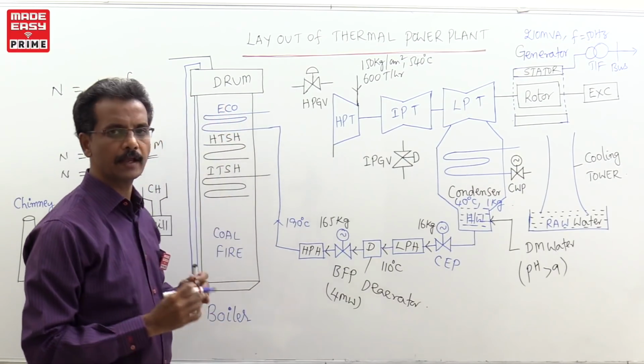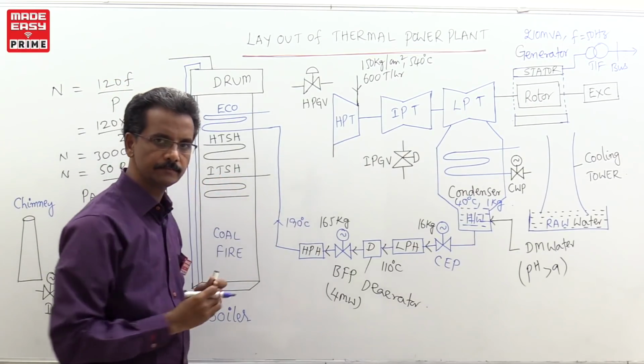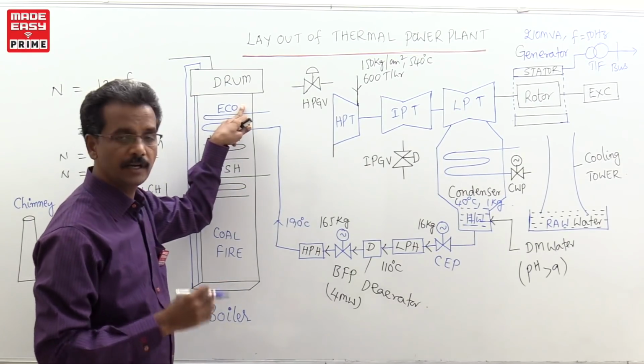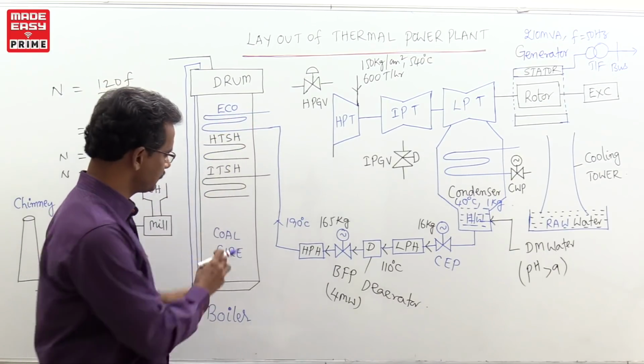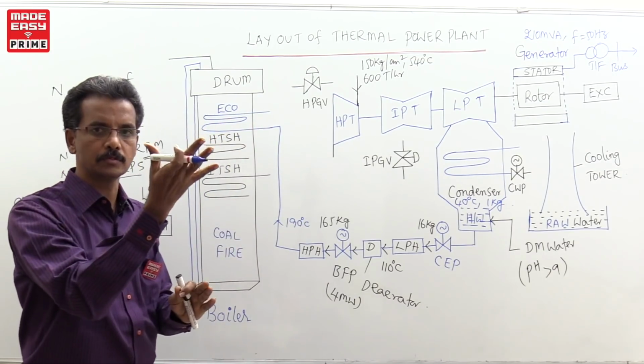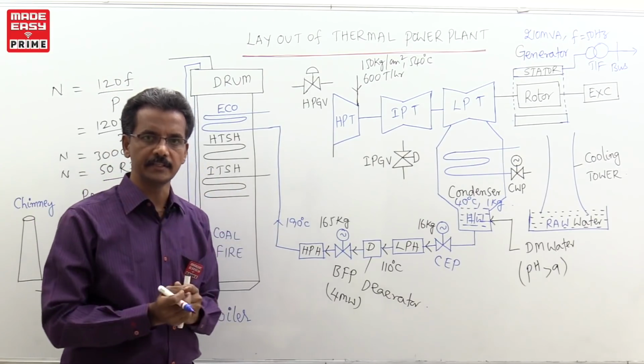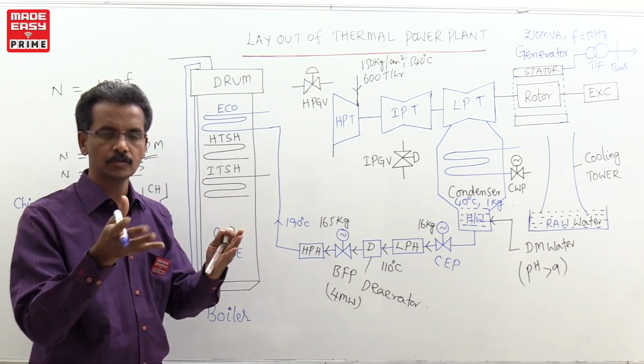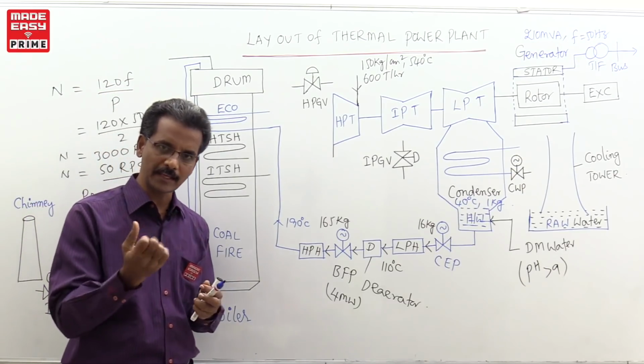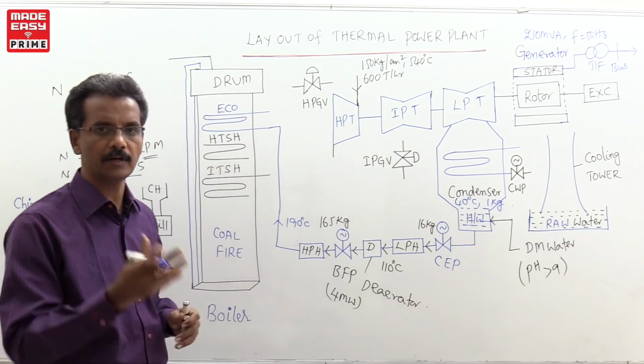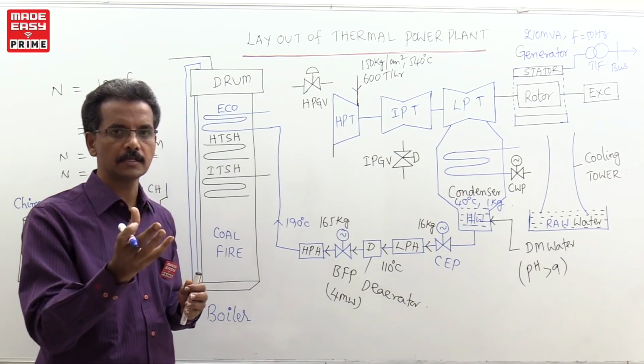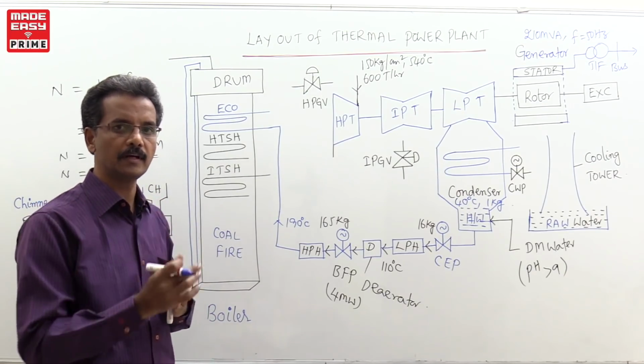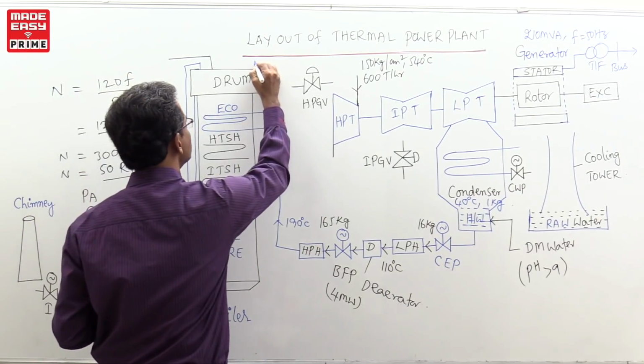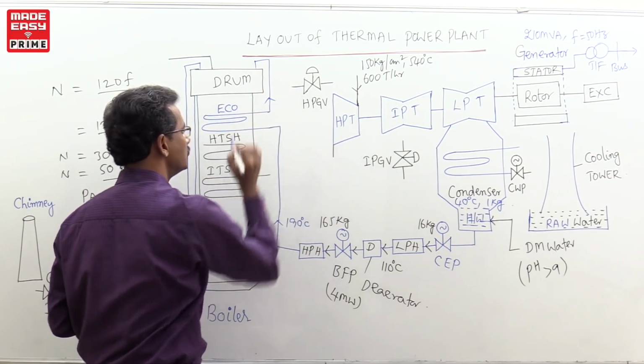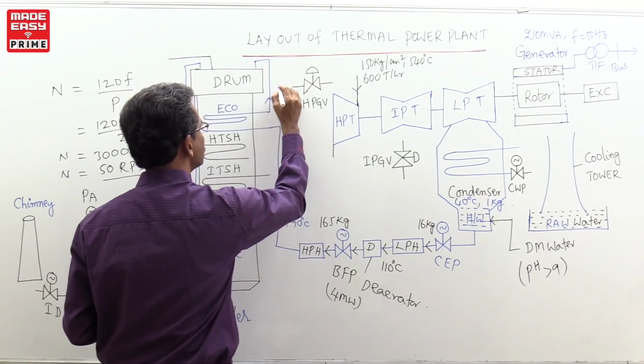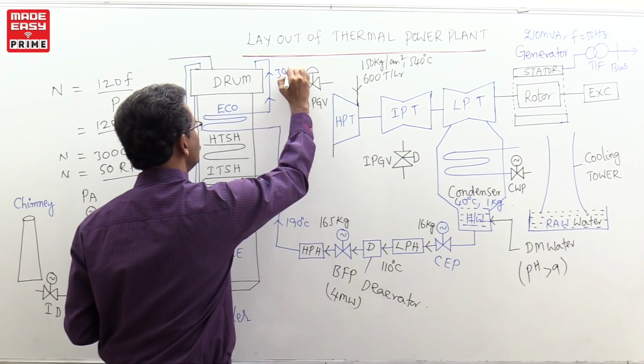The main function of the economizer is to improve the thermal efficiency. Clear? How it improves the thermal efficiency is, when the coal is fired, flue gases are produced. The flue gas has a lot of energy. We should not waste that heat energy. Wherever possible, you are supposed to extract the heat energy. So, by using this economizer, we try to extract the last areas of heat, thereby improving the thermal efficiency. So, at the output of this economizer, the temperature of the water is around 300 degrees centigrade.